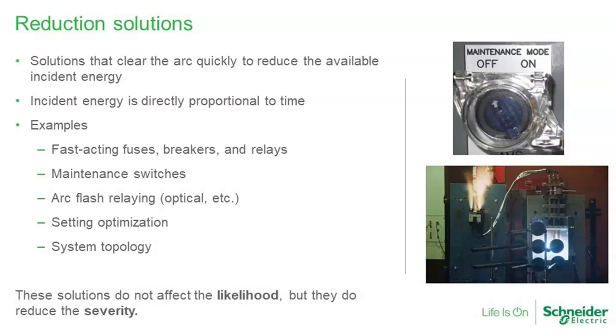One thing to note, the last bullet point down there at the bottom: I said these solutions don't affect the likelihood, but they do reduce the severity. When we talk about arc flash hazards, there are really two components to it, risk and severity. Risk, the likelihood of an event occurring, is really looking more at the probability aspect of it. How likely are we to actually create an arc flash when we're doing whatever it is on this equipment? The other side of the coin, though, is the severity.